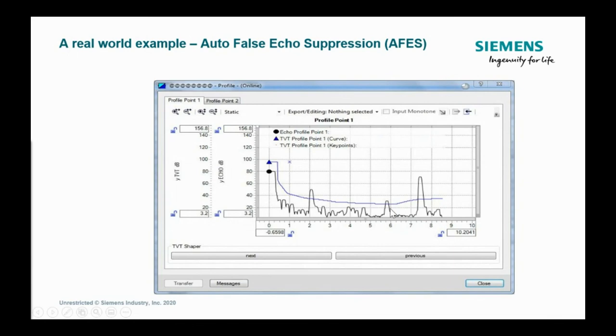What comes in 10-foot sticks? PVC pipe with bell ends. So guess what? Here's an echo. Sure enough, we open up the wet well. 7 feet down, here's an echo off of that first bell end coupling of the two pipes put together, and then exactly 10 feet later, here's another coupling that it sees, and then finally it sees the echo off of the material.